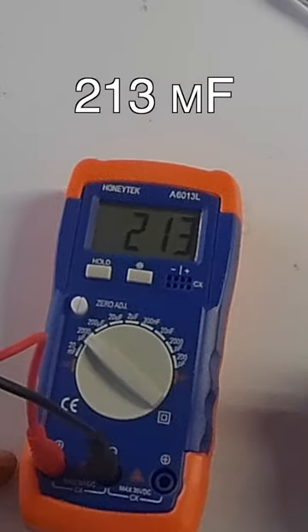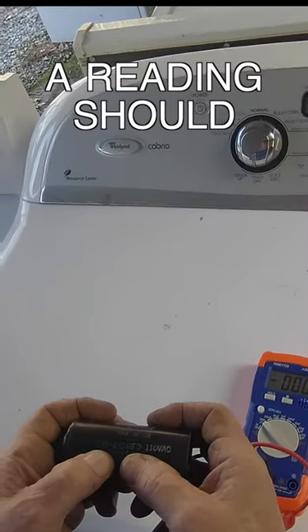So to test this you want to turn this to a sufficiently high level until it comes down and gives you a reading. This is giving me a reading of 213 microfarads. The reading should be between 189 and 227 and it was. So this is a good capacitor.